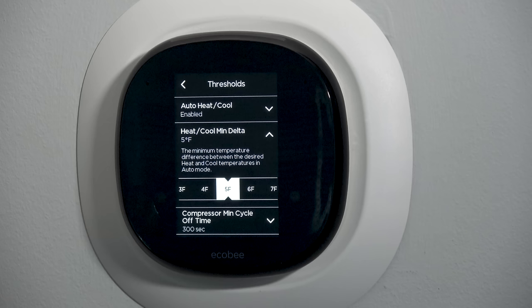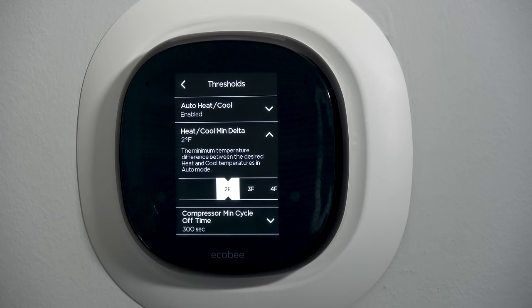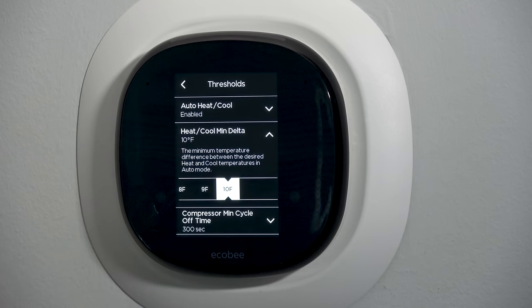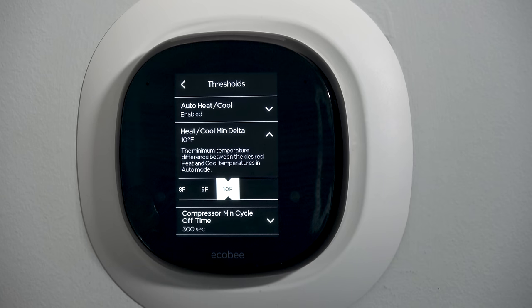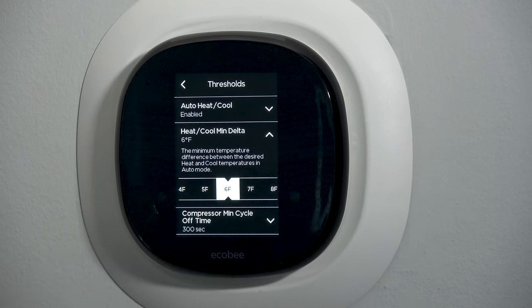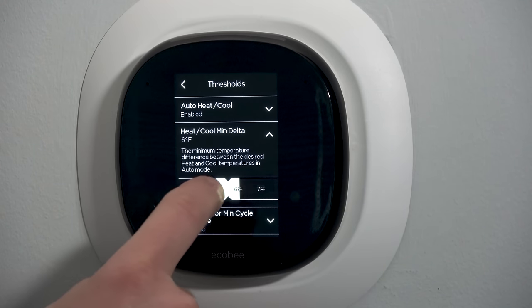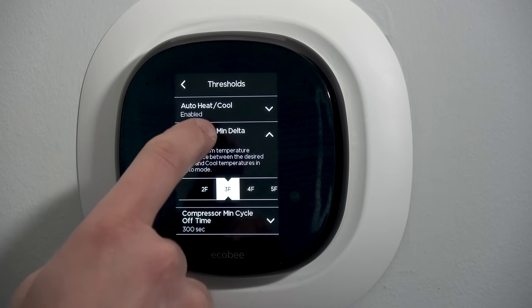Heat/cool minimum delta: what's the minimum temperature that's going to be enforced between the heating and cooling set points? You can make these as close as two degrees — meaning 72 for cooling and 70 for heating. You can make it as high as 10 degrees, so cooling at 75 and heating at 65 with nothing in between. I have my own house set with a six degree span; most people are probably more in the two or three range.